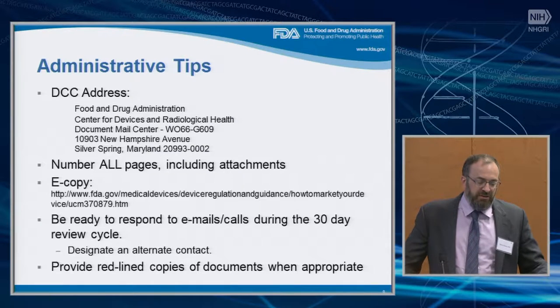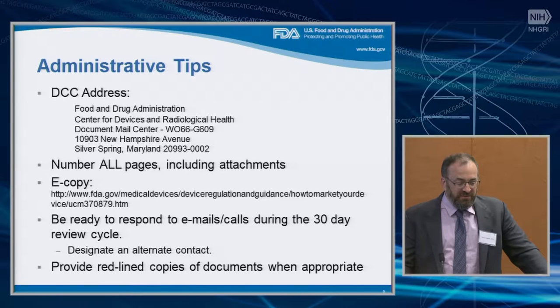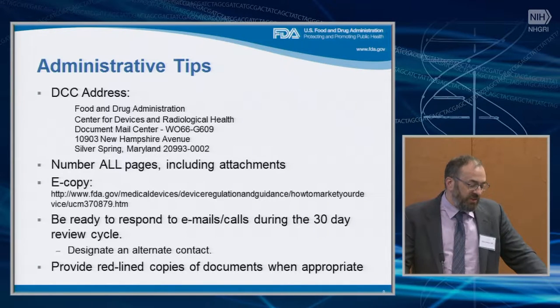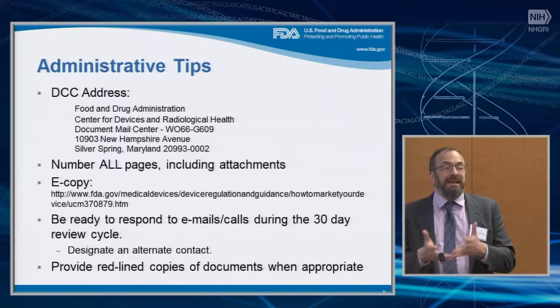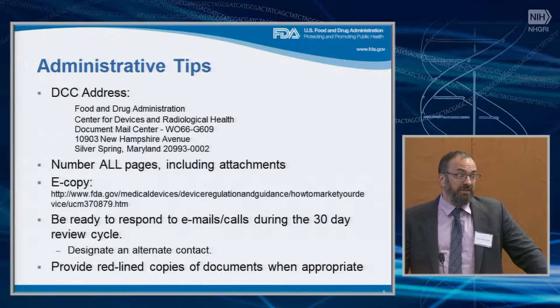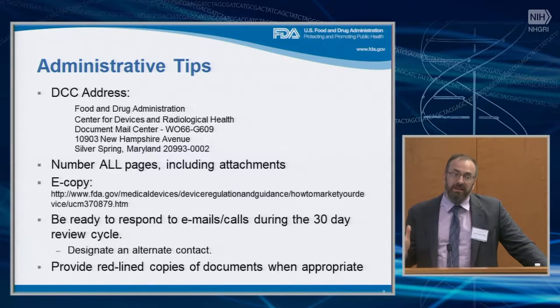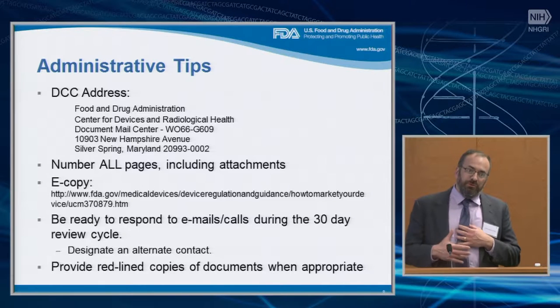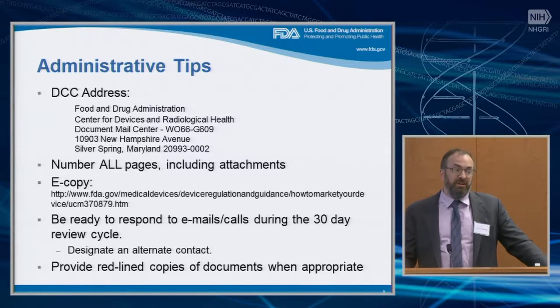One thing I would point out: you should be ready to respond within our 30-day review window. We have to make a decision within 30 days, which means we will be emailing or calling you if we need clarification on something. You will specify a contact and should be ready to respond — you may get a request saying we need to know X, and you may need to get it to us the next day so the decision can be made within the deadline. Have an alternate contact so if you're not available, somebody will be around to respond. If you're responding to deficiencies from a previous IDE or making changes, you should provide redline copies so we can see what has been changed.